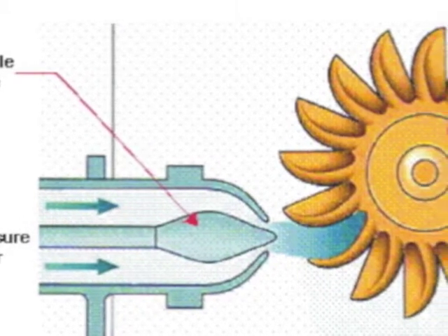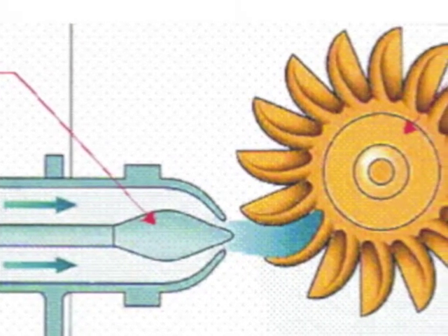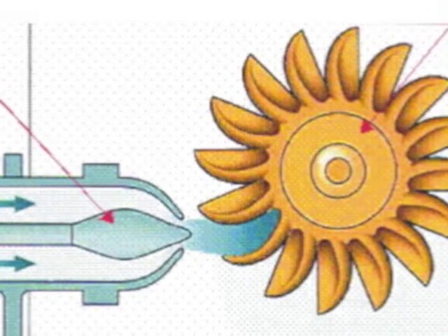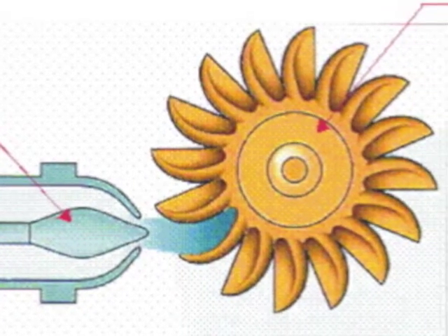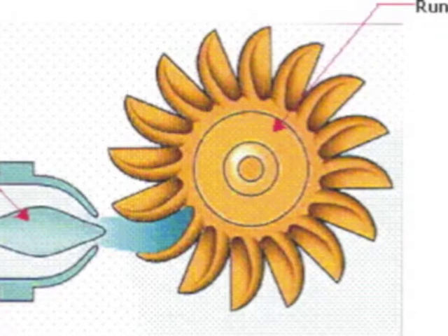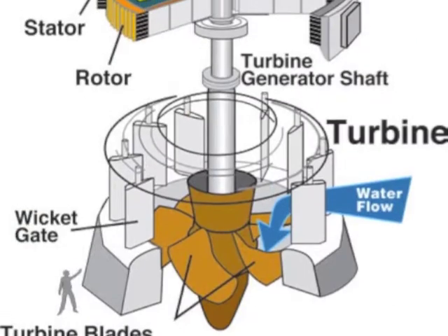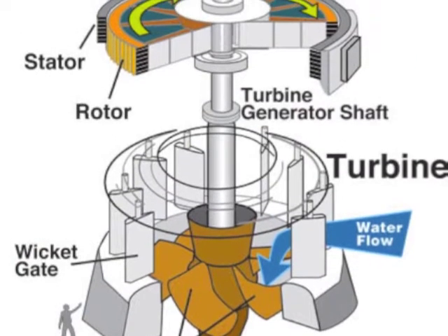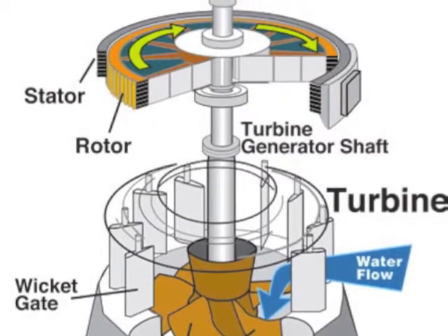Different types of turbines can be selected based on the volume and height of standing water on site. The two most prominent types are reaction turbines, which are better in lower head and higher volume applications, and also impulse turbines, which are suited for high head and low volume conditions.